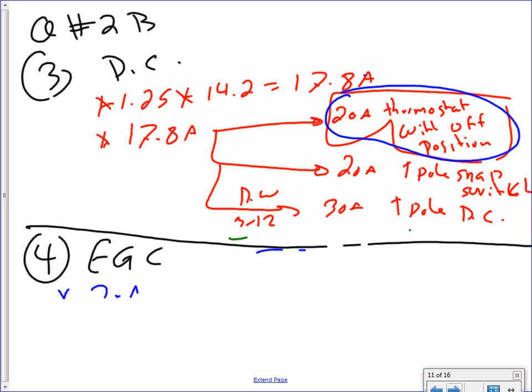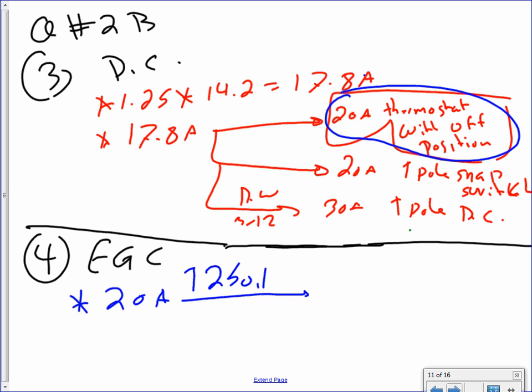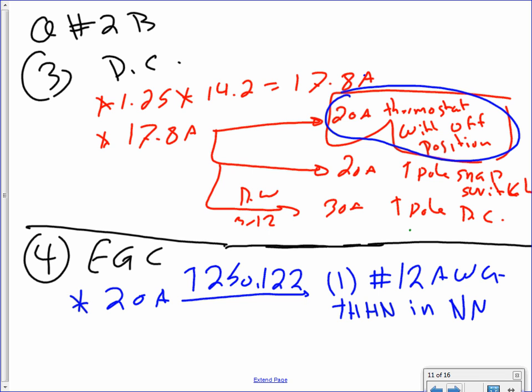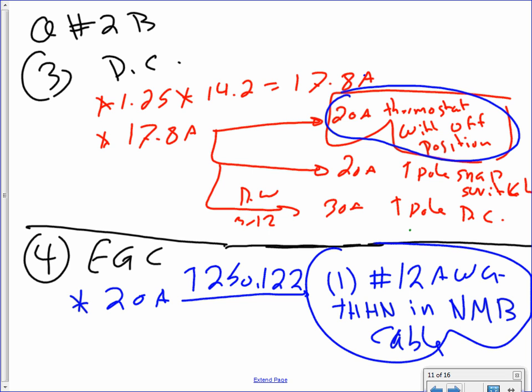Okay, last thing is the overcurrent protection device. On the test, guys, for an example like this, you just say a thermostat with an off position. So what you have to tell me, okay, what was it? That 20 amp, you're going to take the 20 amp to Table 250.122. That will get you one conductor number 12 AWG THHN in the NM cable. That's it.